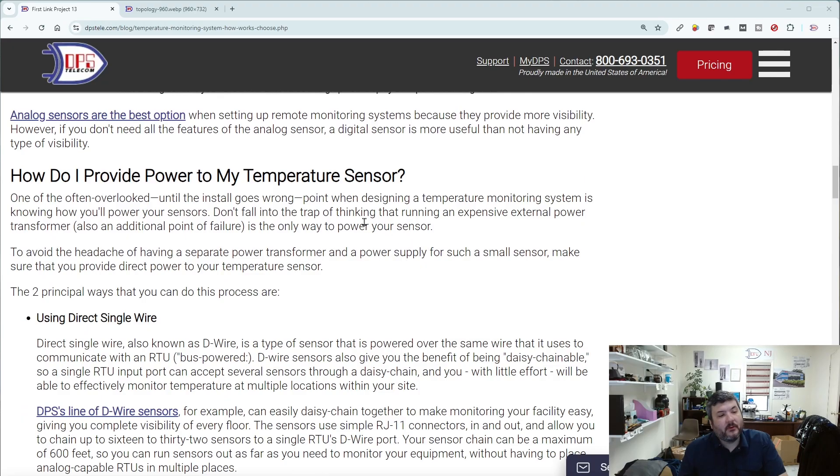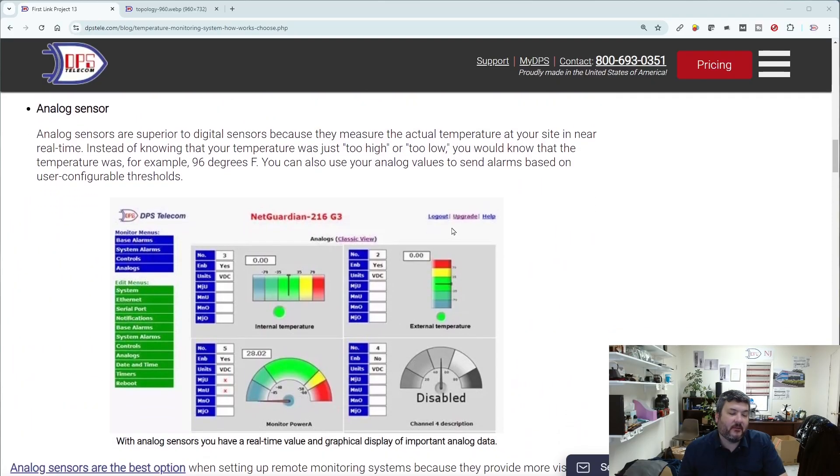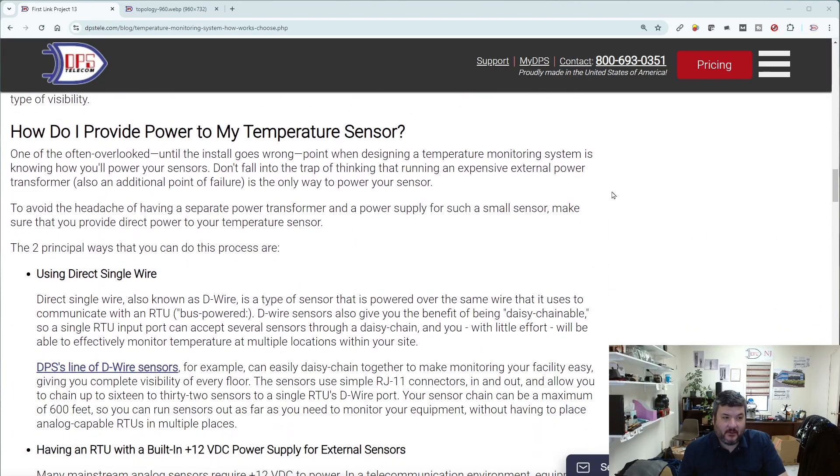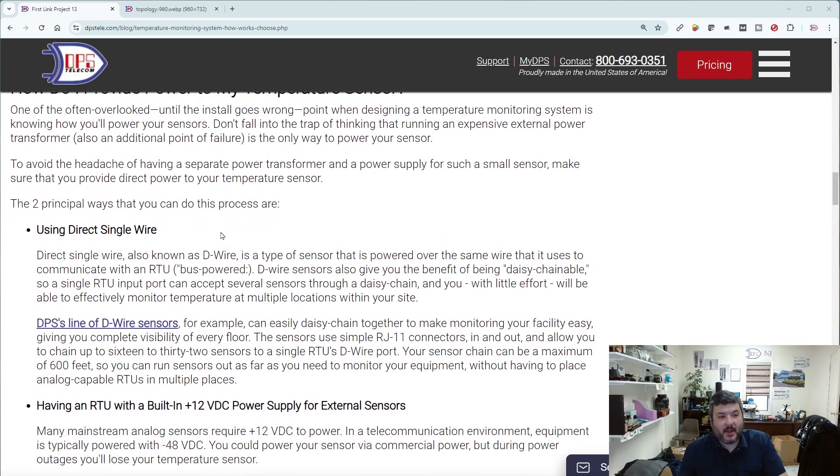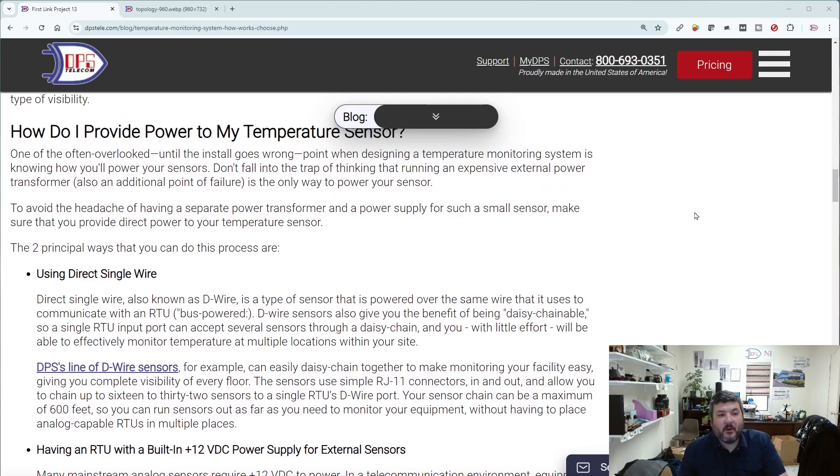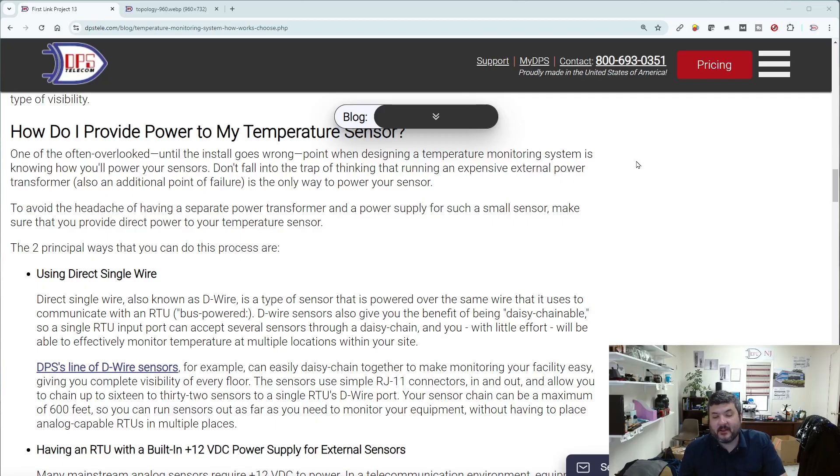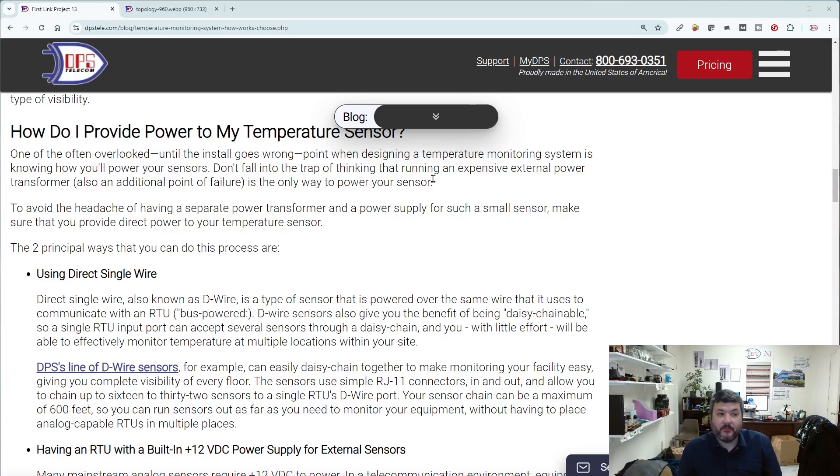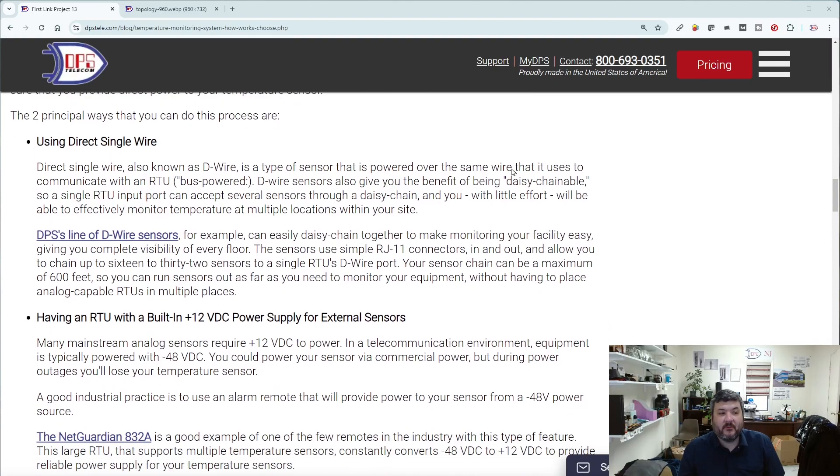How do we power this? The one challenge with analog sensors is going to be getting them power. What does it mean to have to power a temperature sensor? The good thing about discrete sensors in some cases, if they are truly mechanical in the way that old traditional thermostats were before they became electronic, you may not need any power at all. This is just a piece of metal that when the temperature causes it to deflect enough, it clicks together and provides electrical connectivity, and that can be picked up by a remote telemetry unit like the DPS NetGuardian line.